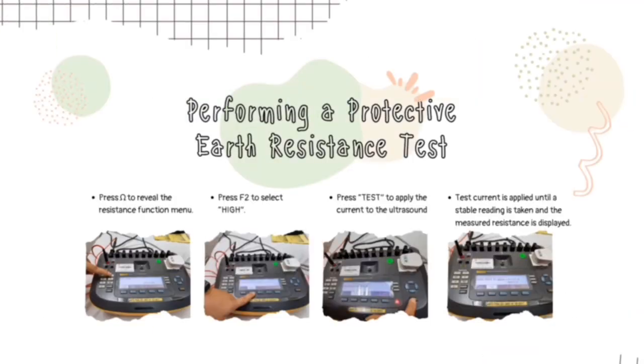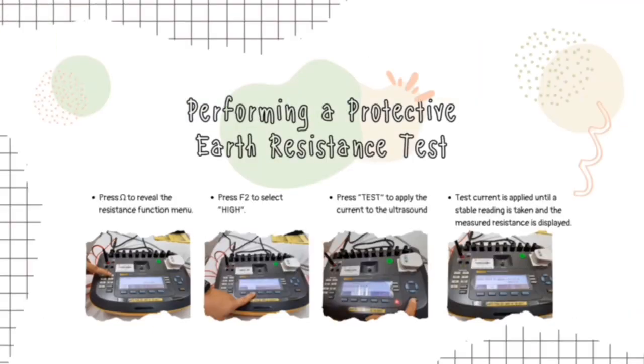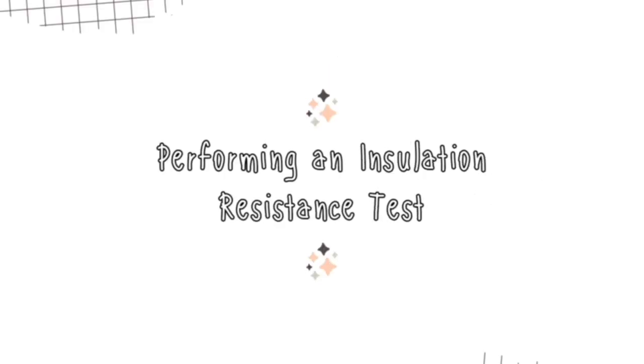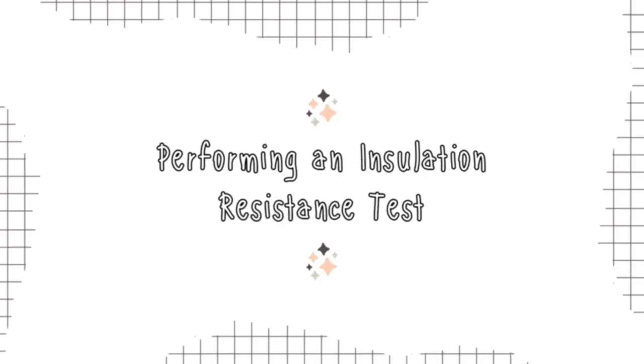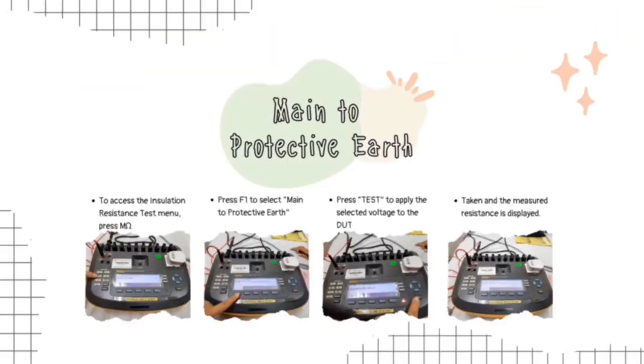For performing a protective earth resistance test, we must press the ohm symbol to reveal the resistance function menu on the analyzer. First, press F2 to select high, and then press the test button to apply the current to the ultrasound. Then, test current is applied until a stable reading is taken and the measured resistance is displayed as in the figure.